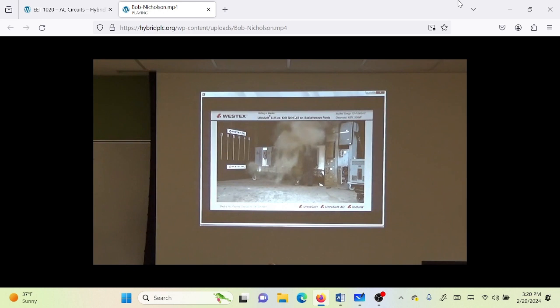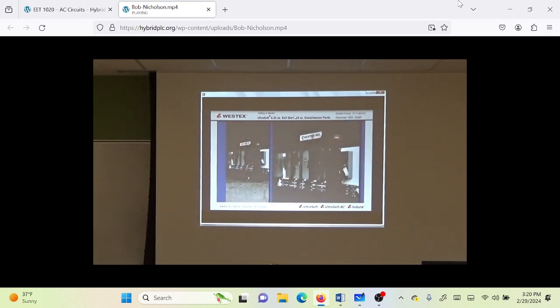You can see a huge amount of molten metal, even in real time, all over the floor and thrown an enormous distance from the disconnect. Some of that molten metal ended up in excess of 40 feet away. But again, no fire on the garments. No break open. All right, here we have a split screen slow-mo, 3,000 frames a second. The arc at first is a torso event. You can see a huge amount of molten metal being thrown a huge distance from the arc gap over his left shoulder. Meanwhile, the arc has hit the mannequin, traveled down the body, and becomes the...